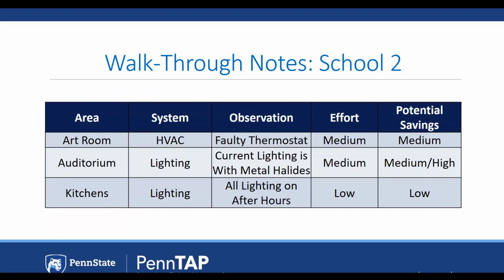In School 2, however, you can see that there is a similar circumstance where current lighting is on after hours in the kitchens. However, this is a low potential savings because this was only found in one of the areas, not the whole building. It is important to consider that every building is unique and should be treated as an individual. You cannot assume behaviors at one location exist at a different location.